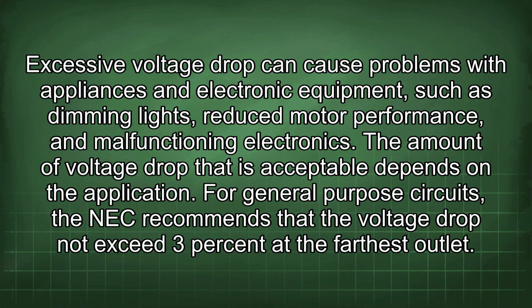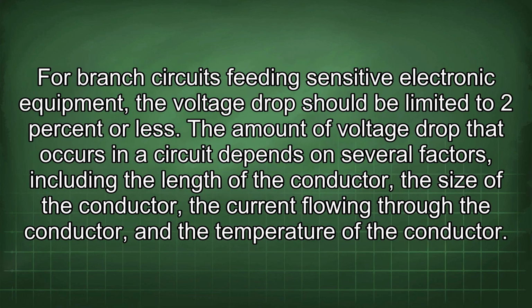For general-purpose circuits, the NEC recommends that the voltage drop not exceed 3% at the farthest outlet. For branch circuits feeding sensitive electronic equipment, the voltage drop should be limited to 2% or less. The amount of voltage drop that occurs in a circuit depends on several factors, including the length of the conductor, the size of the conductor, the current flowing through the conductor, and the temperature of the conductor.